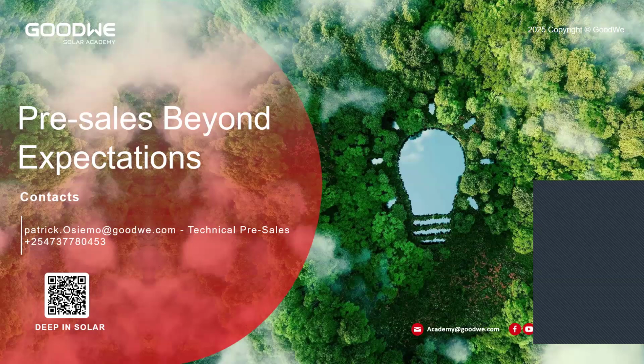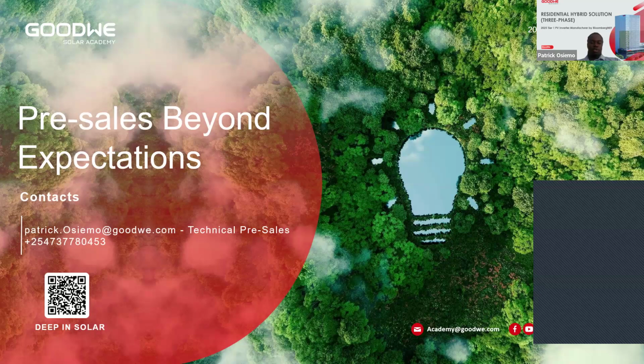Someone is requesting you to repeat on the ETLV and MPPTs. The ETLV has up to 3 MPPTs. Each MPPT has one input, and on each input we can handle up to 20 amps of current. If you're doing 20 amps of PV, that is a high power PV. Most of the PVs we have are around 16 or 17 amps. So our technology is ahead of the PV market. We can handle high power PV panels without clipping the generation.